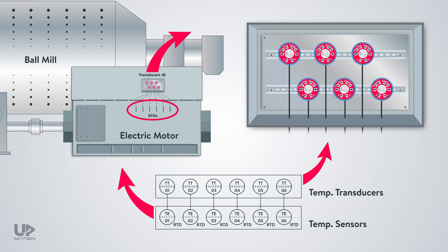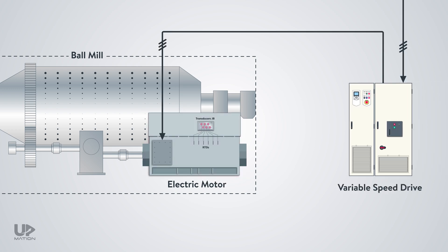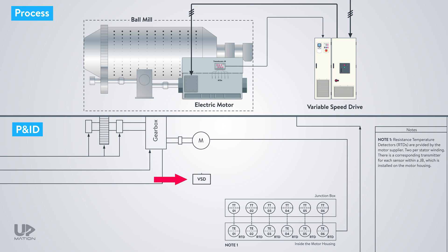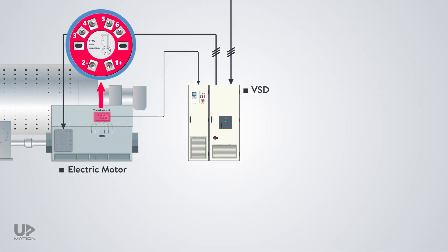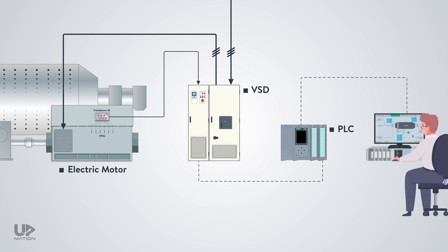We're not done with this part yet. As the ball mill electric motor is controlled by a variable speed drive, or VSD, I decided to connect its temperature transducers directly to the VSD. Therefore, I will do so in the P&ID — first consider the VSD and then connect the transducers to it. I also want to send the signals from these transducers to a PLC card and then transmit them over a network between the VSD and PLC.